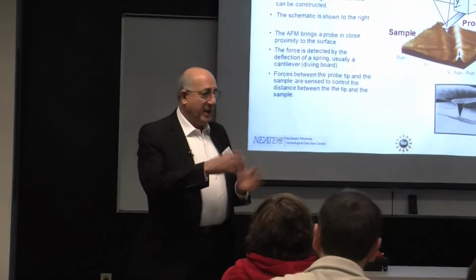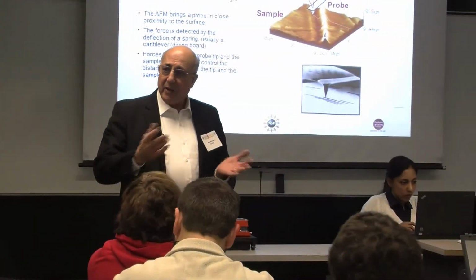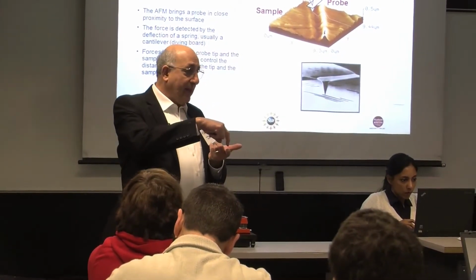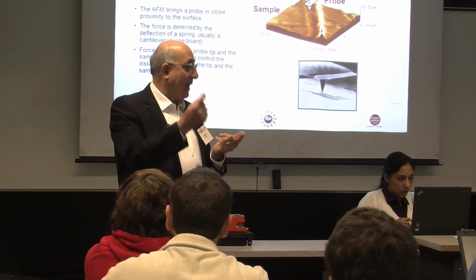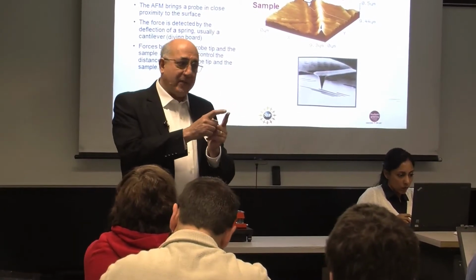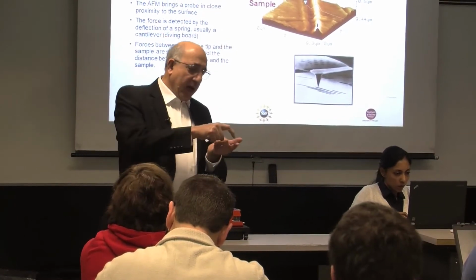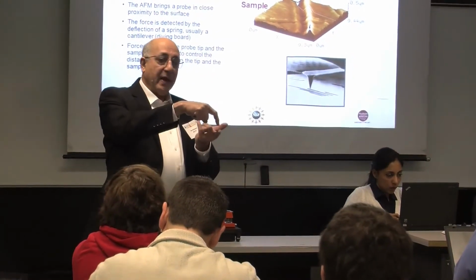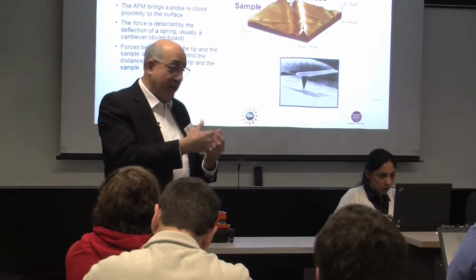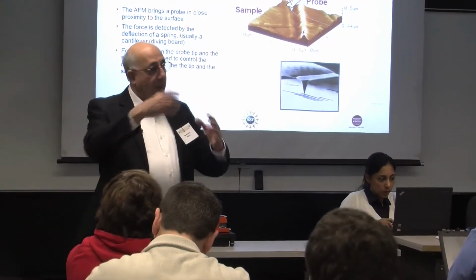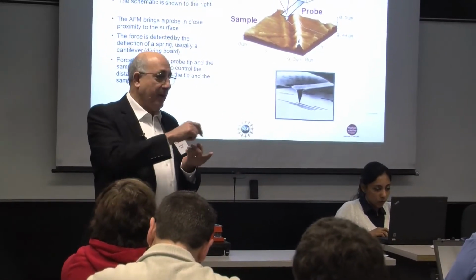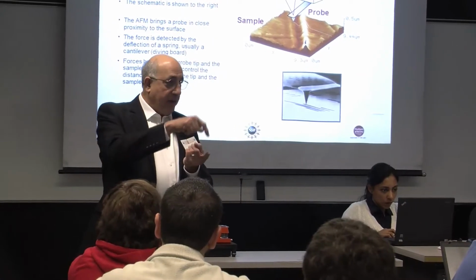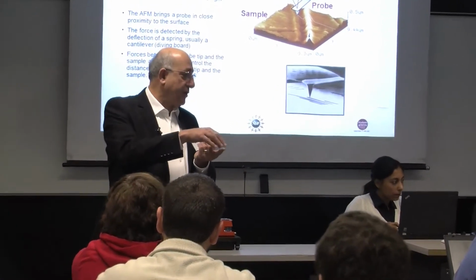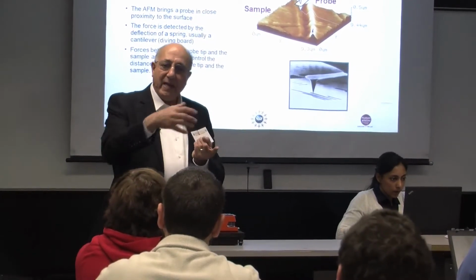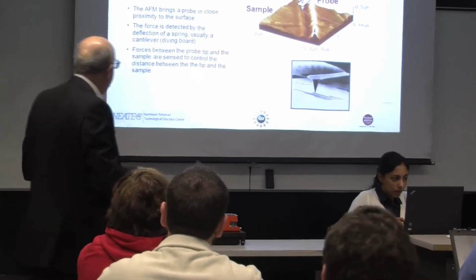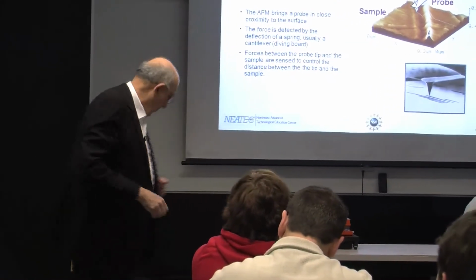Normally there are different types of operation of this device, but in one type of operation, at the atomic level, when you have any two materials, you have electrons, and they have attraction and repulsion. So there is a force between the tip and the sample that we can measure with the AFM, and we can make a plot of it. One important thing about the AFM is that the force between the tip and the sample at any moment should be constant, if possible. We do this with a mechanism called feedback. We have a control system to make sure that the force between the tip and the sample remains constant.